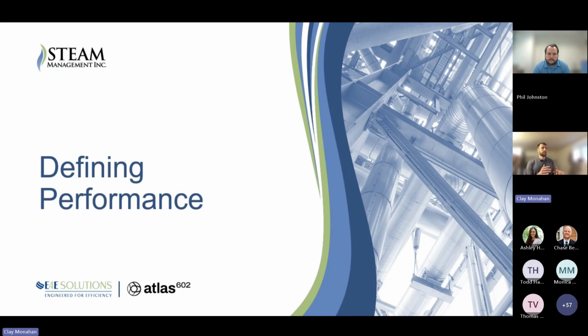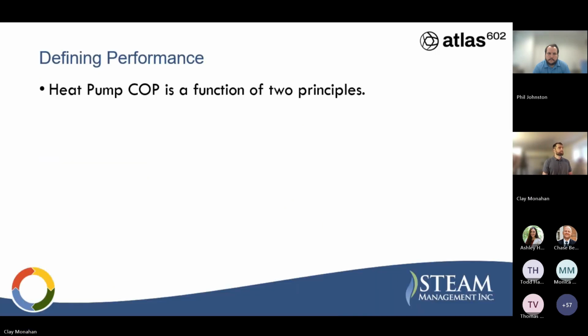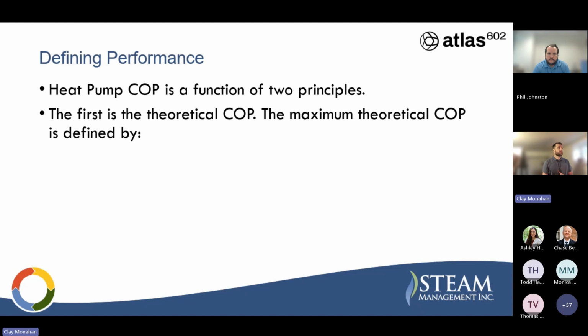And now we're going to get into defining the performance with a few critical parameters. So heat pump COP is a function of two basic principles. First is the theoretical COP. What's the maximum possible COP we can achieve? And that's just going to be defined by the temperature conditions that the heat pump is seeing. So that maximum theoretical COP is just going to be the hot temperature that we're trying to achieve divided by the lift, or the temperature delta across the heat pump, the hot temperature minus the cold temperature.